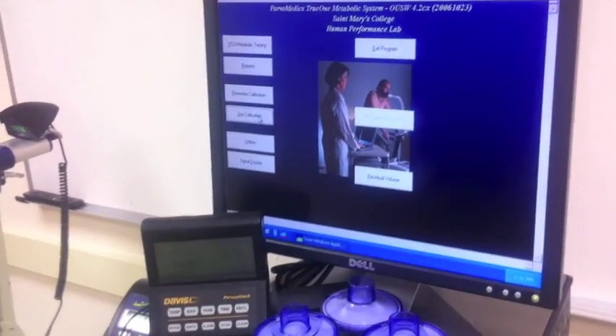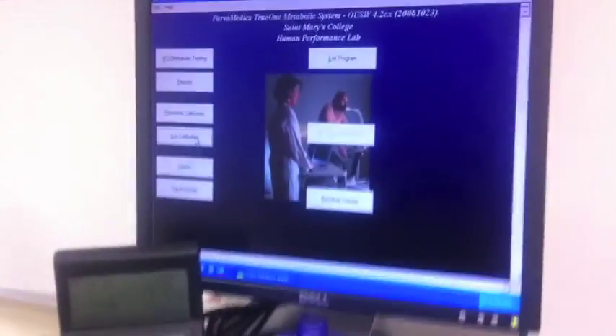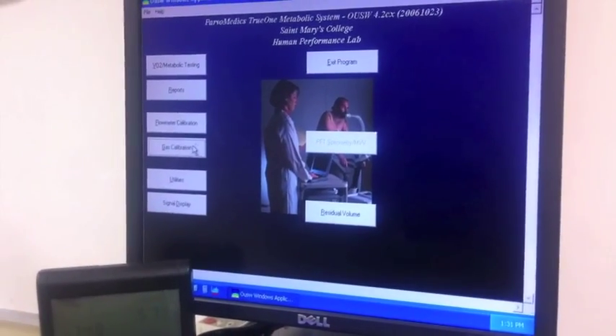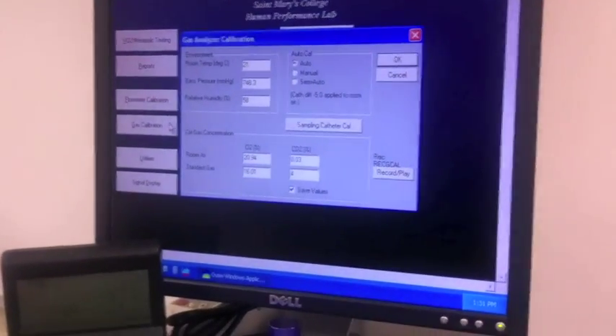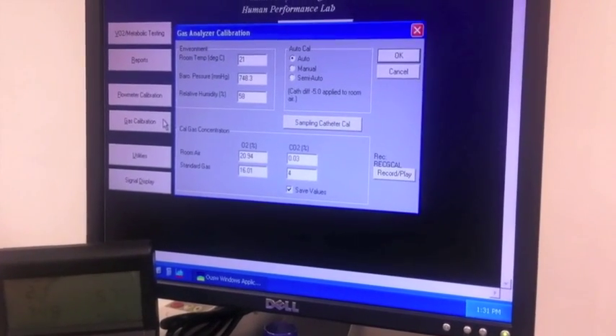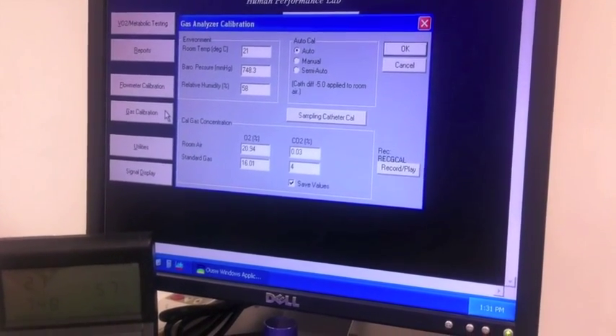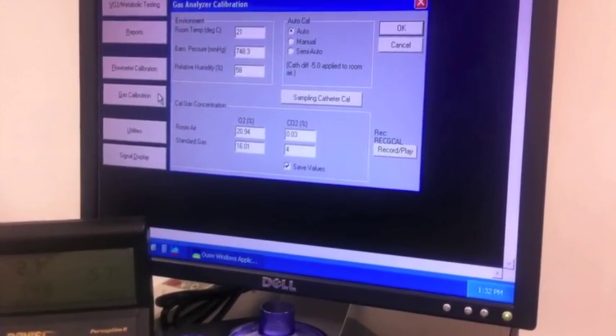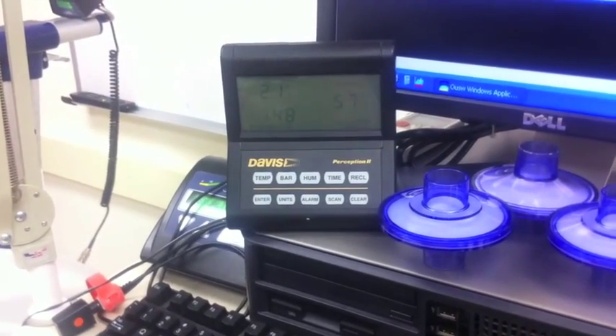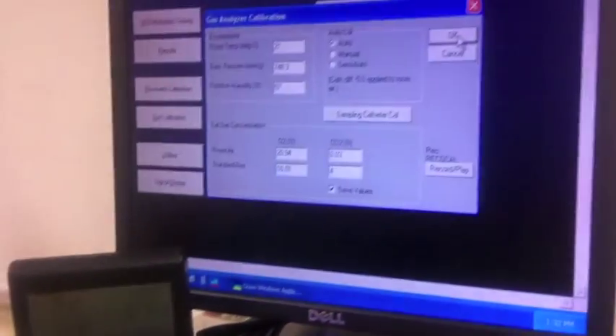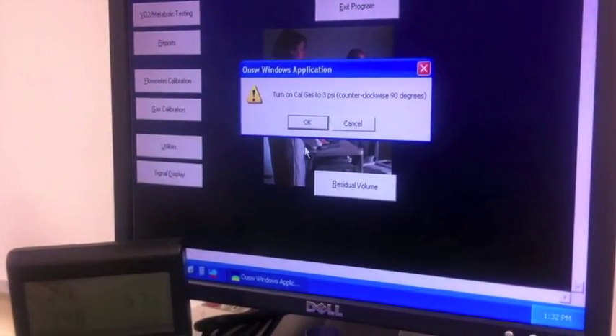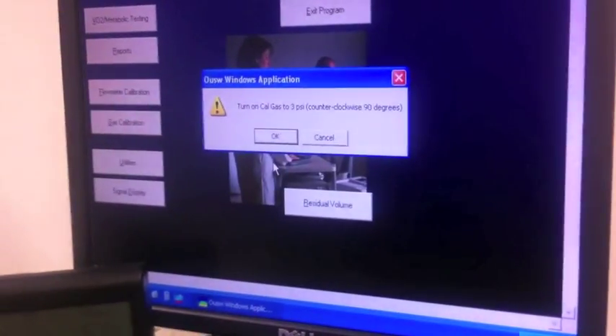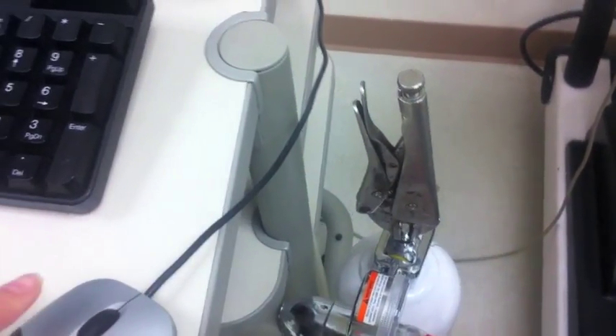Part 2 of the calibration is the gas calibration. So you will begin by clicking on the gas calibration tab on the desktop. A window will appear asking for the temperature, humidity, and barometric pressure. These again can be found on the Davis Perception machine, and you will plug in the numbers and press OK after you finish. Then it will ask you to turn on the CalGas counterclockwise 90 degrees. Then press OK.